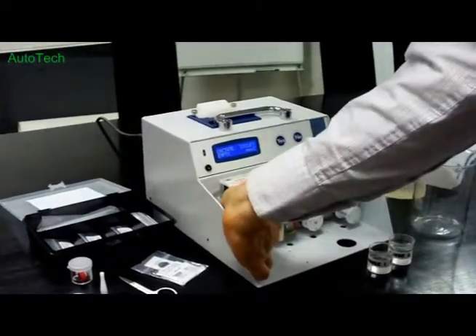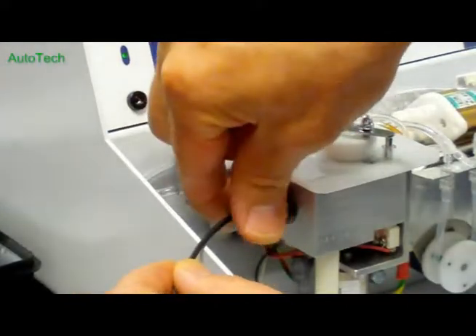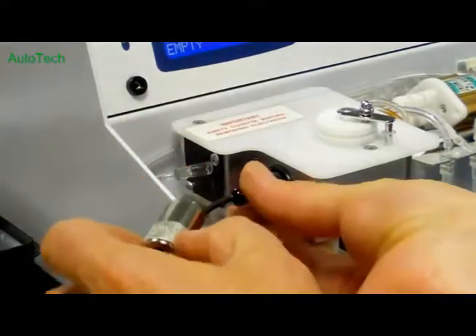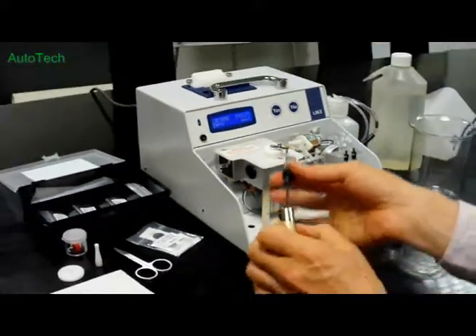So when that's complete, unplug the electrode from the bulkhead, and turn the bayonet fitting until it releases, and then withdraw the electrode.